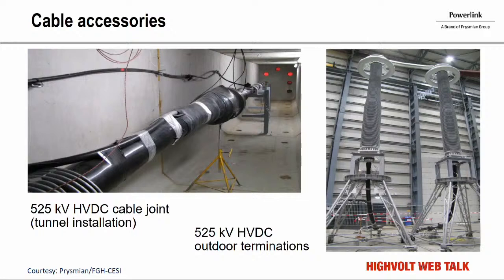What are the critical components of a DC cable system? The cable itself is very well tested and of good quality. The main problem is the joints and the end terminations, and the laying of the cable. During these steps, a lot of manual work is required on-site, and it is very difficult to achieve high quality consistently. This is why we must test afterwards using different methods to find mistakes made during this manual assembly work.